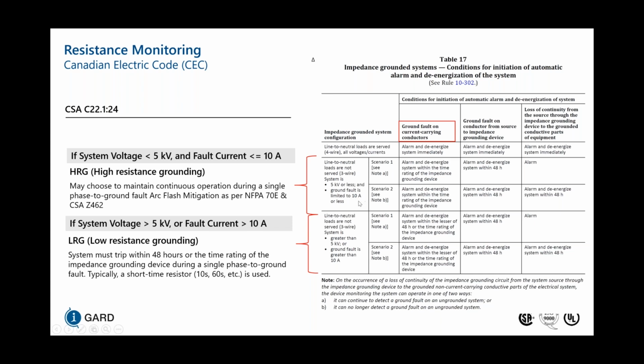In terms of impedance grounding system configurations, here it indicates the area where a lot of people are taking advantage, which is for high resistance grounding on this particular row. In this case, for ground faults in the system, we alarm and de-energize the system within the time rating of the impedance grounding device. But if the unit is rated for continuous use, then we only alarm the condition of the ground fault without having to de-energize, which allows for process continuity.